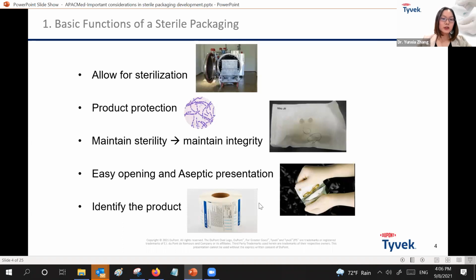Let's start by having a look at the basic functions of sterile packaging. This is also addressed in ISO 11607. For those who may not be quite familiar with ISO 11607, this standard addresses packaging for terminally sterilized medical devices in terms of materials, design, and process validation. These elements are very important to keep in mind when selecting or designing a sterile barrier system.